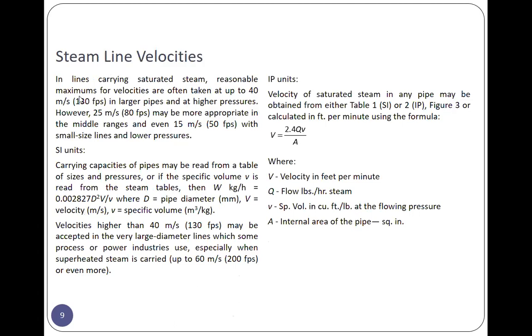Steam line velocities in lines carrying steam, reasonable maximums. Okay, tama. Velocities are often taken up to 40 meters per second, 130 feet per second, in larger pipes and at higher pressure. However, 25 meters per second or 80 feet per second may be more appropriate in middle ranges, and even 15 meters per second or 50 feet per second with small size lines and low pressure.